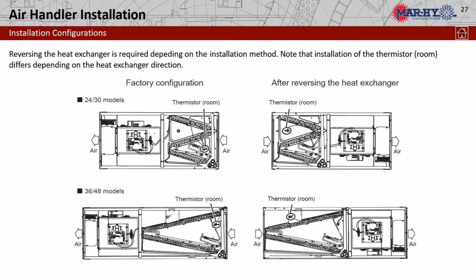It shows it a little better here. They're highlighting the room thermistor in each of the applications we've talked about, at least horizontally here. You can see that they've relocated the thermistor depending on which way the air flows through the coil. Pretty basic stuff. It's a fairly simple change if you need to move from one location to the other. You would disconnect your sensor, pull your coil out, swap your coil direction, and then relocate the sensor in the other knockout.